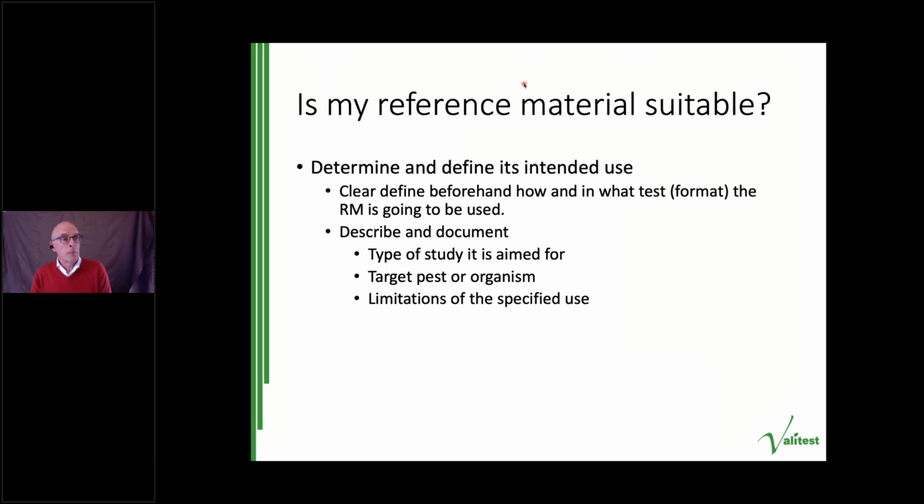So if you get your material, and especially if you want to start producing it for test performance studies, you have to ask yourself, is the reference material that I want to start using or supplying really suitable? And one very important thing to start off with is you have to determine and define its intended use. You have to clearly define beforehand how and in what test format the reference material is going to be used. That needs to be carefully described and documented.